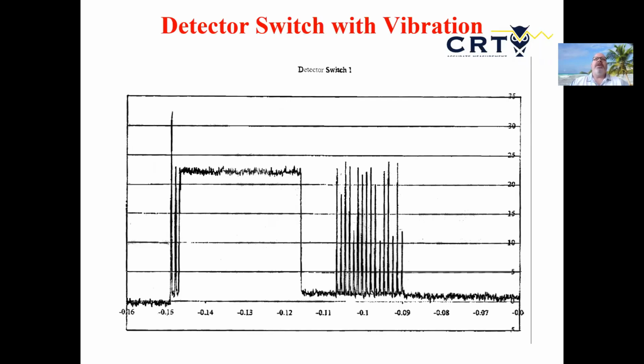I wanted to show one of the coolest pictures I have. This is a detector switch, from a prover, and this is what it looks like when the ball passes by. The detector switch does what we call a slap, creating a signal on the outlet as the ball travels at high velocity. This is what we can see inside the flow computer, and it can also cause a miscalibration.